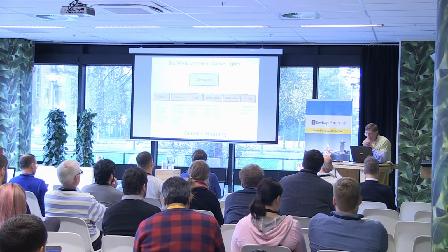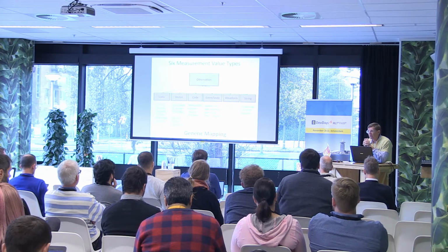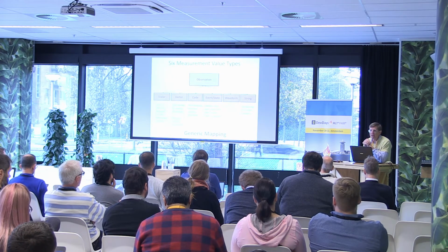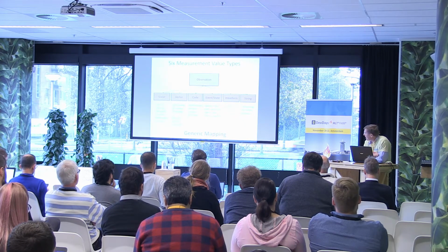This is probably the most complicated measurement because HL7 has no way to represent such a measurement. It is unique to device measurements. There's no way to map this in HL7. So we actually had to develop a second code scheme to convert these state measurements into something HL7 could understand. This is the same for CDAs and for FHIR, and we use that. These measurements are not that common, so that's a good thing.